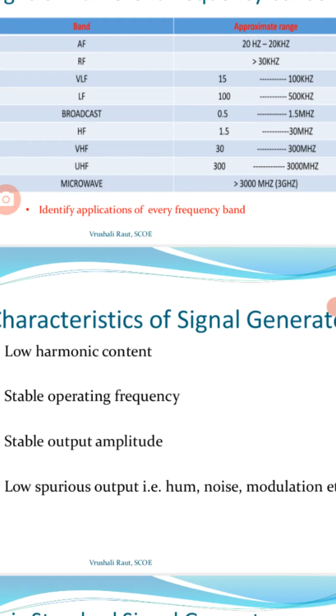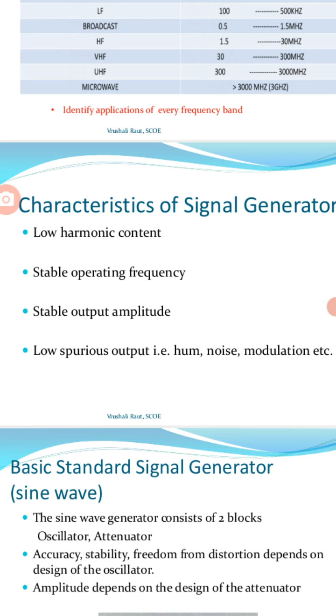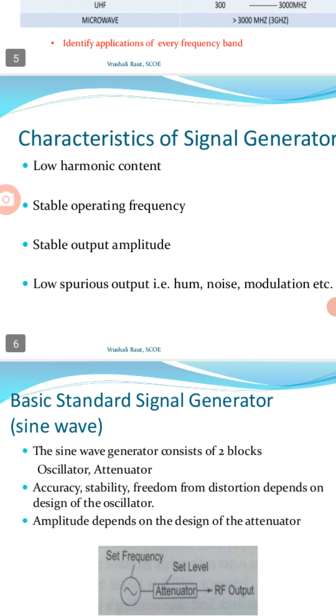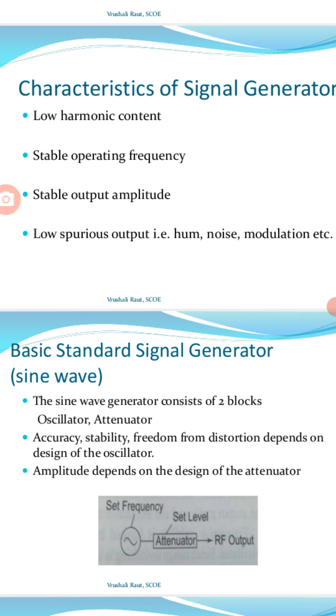Characteristics of signal generators. Low harmonic content is the first characteristic of a signal generator. Then stable operating frequency is another characteristic of a signal generator. Stable output amplitude is a very important characteristic of a signal generator. Without stable output amplitude, there will not be perfect measurement and your instrument will not function properly. If output is not stable, then in a mobile you will find there is intermittent voice or a broken voice.